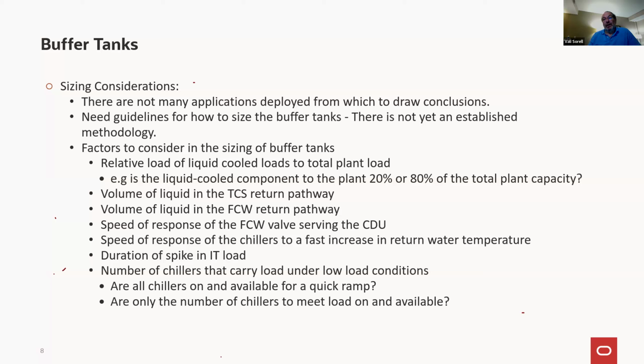So the simplicity of doing it with temperature sensors, and by the way, even though I'm talking about putting a temperature sensor at the inlet to the buffer and a temperature sensor to the outlet, we have other temperature sensors throughout the loop. And we have pressure sensors. We have a lot of sensing elements. So probably the most appropriate way is to do some discriminated control where you're looking for the highest value or the quickest rise in temperature anywhere in that loop. And that can become the trigger to do that.